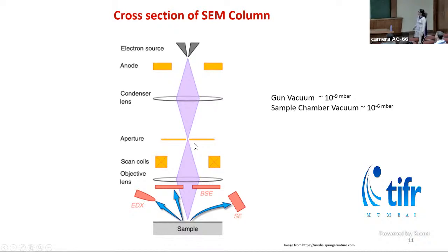Then there are apertures which eliminate the off-axis electrons, and there are scan coils because we need to scan the sample, and the objective lens is the final probe-forming region. Then these are the various detectors used for detecting different signals. This whole assembly is kept in a vacuum, where the gun is of the order of 10 to the power minus 9 millibar, and the sample is at the order of 10 to the power minus 6 millibar.